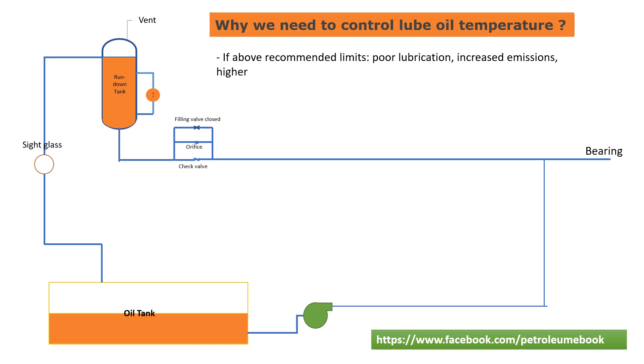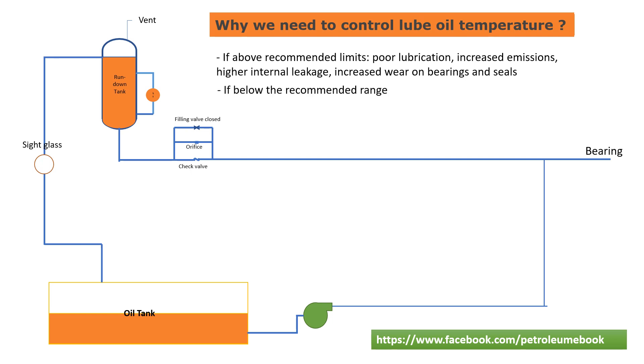Lube oil temperatures above recommended limits cause lower oil viscosity, leading to poor lubrication, increased emissions, higher internal leakage, increased wear on bearings and seals, and thermal degradation of seals and other components.